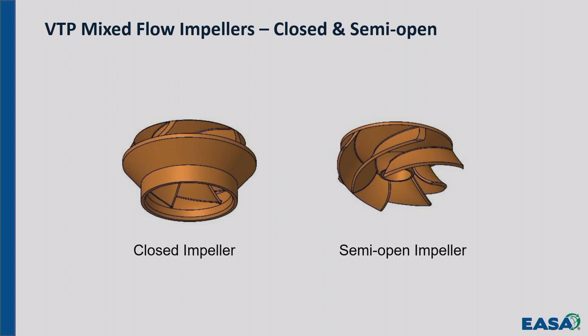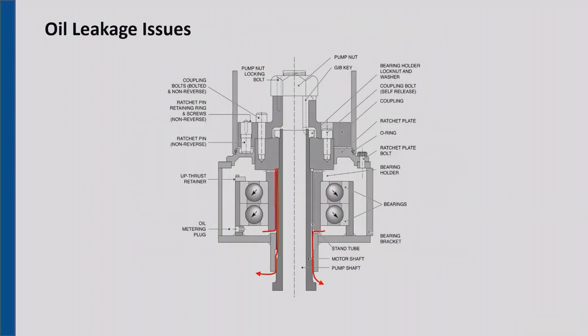So my point there was to dispel the notion that might have been out there that all you have to do is raise the pump shaft to take the load off the motor. And I don't have to dispel that notion because you didn't have it. That's okay. Now you know about it. And we'll cover the issue of setting that pump shaft lift here in a minute.